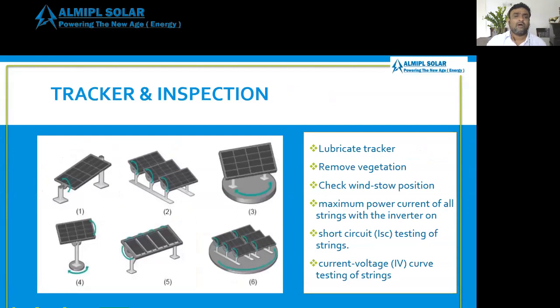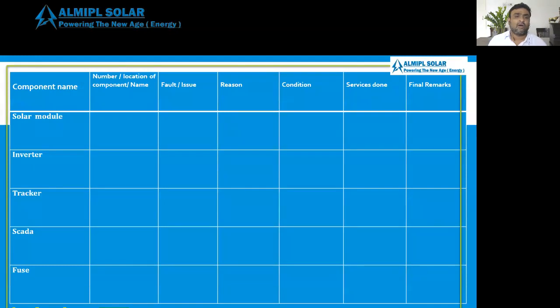Tracking inspection: lubricate the tracker, remove vegetation, check the wind stow position. Maximum power current of all strings with the inverter on, short circuit current ISC, testing of strings, current-voltage curve testing of strings. So we need to prepare this type of graph, and we need to check frequently.